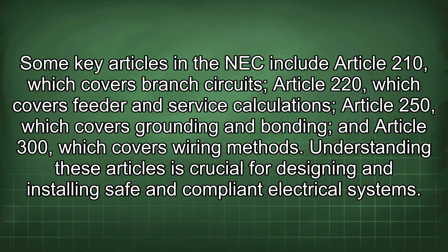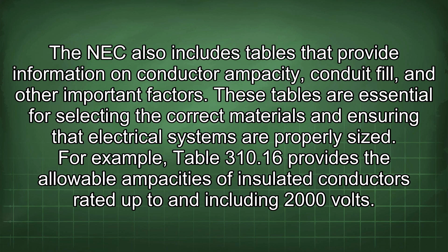The NEC also includes tables that provide information on conductor ampacity, conduit fill, and other important factors. These tables are essential for selecting the correct materials and ensuring that electrical systems are properly sized. For example, Table 310.16 provides the allowable ampacities of insulated conductors rated up to and including 2000 volts. This table is used to determine the maximum current a conductor can carry safely based on its size, insulation type, and ambient temperature.